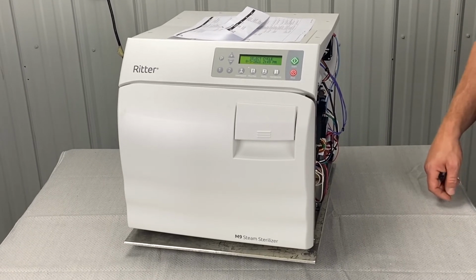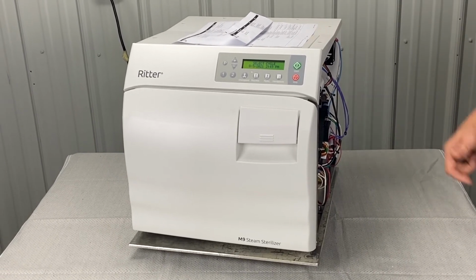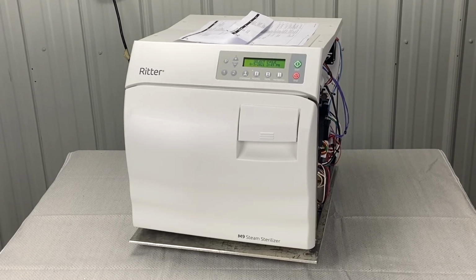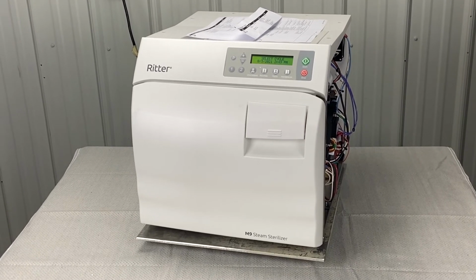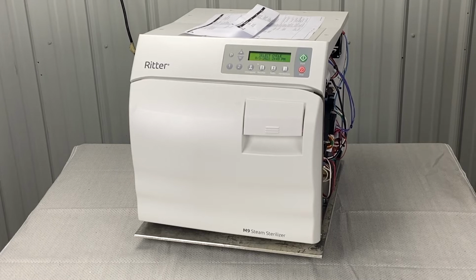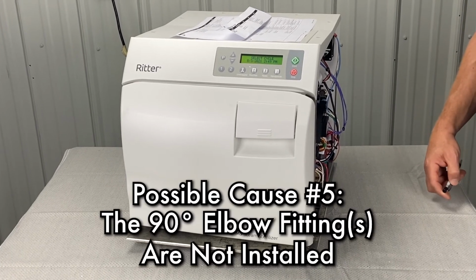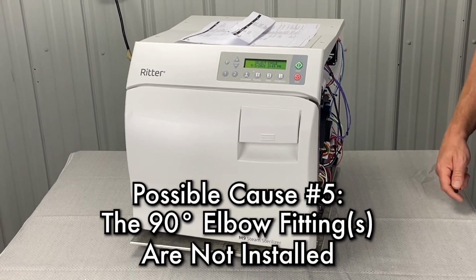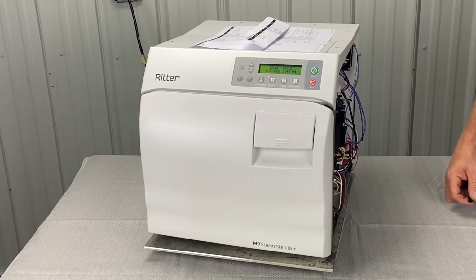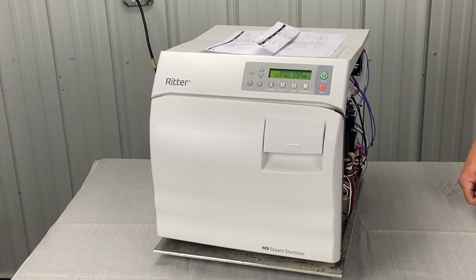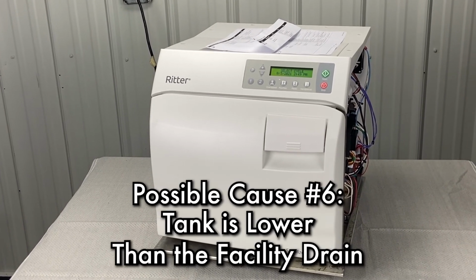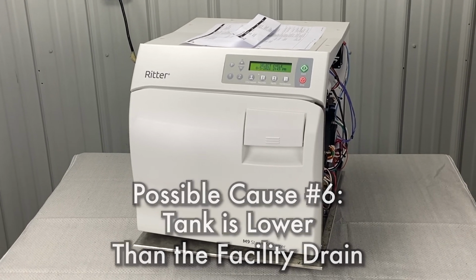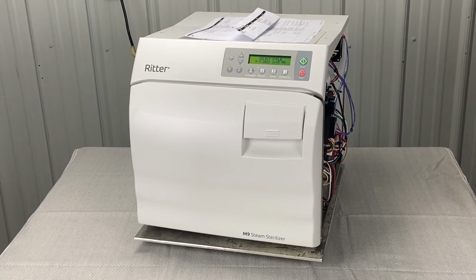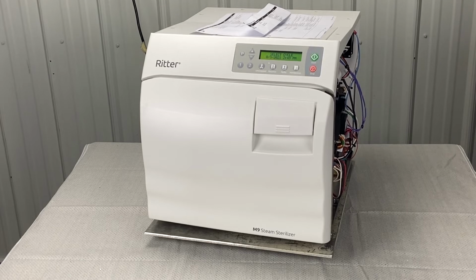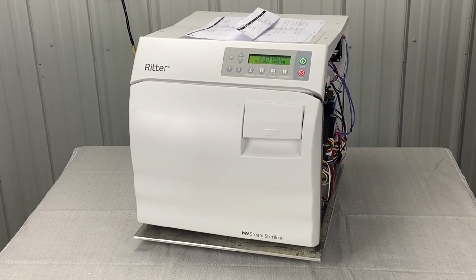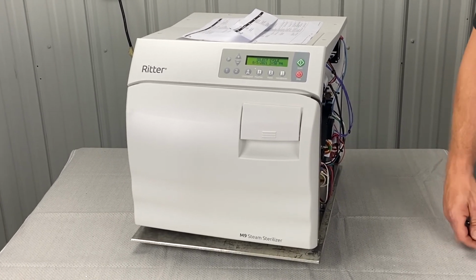All this stuff, these deeper dives here, you're going to want to get a technician to do. Call somebody, have them come out to the office and check the VistaCool system. Check if the 90-degree elbow fittings are installed on the tank. Install 90-degree elbow fittings. The tank is lower than the facility drain. Check if tank is higher than the facility drain. So you're going to want that tank lower than the facility drain. That's all I can pretty much say.